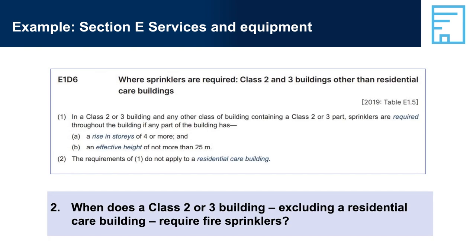Question 2: When does a Class 2 or 3 building, excluding a residential care building, require fire sprinklers? A Class 2 or 3 building, excluding a residential care building, requires fire sprinklers if any part of the building has a rise in storeys of 4 or more, even if the effective height is less than 25 metres. If the building has an effective height of more than 25 metres, sprinklers are also needed.